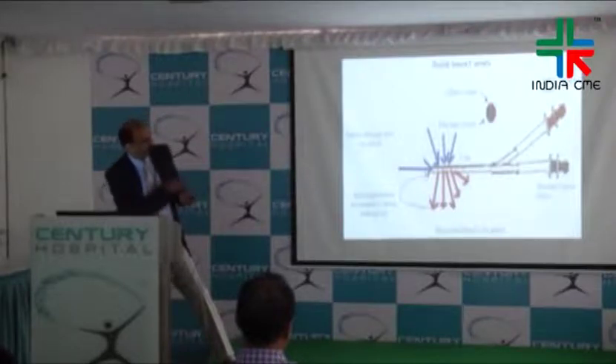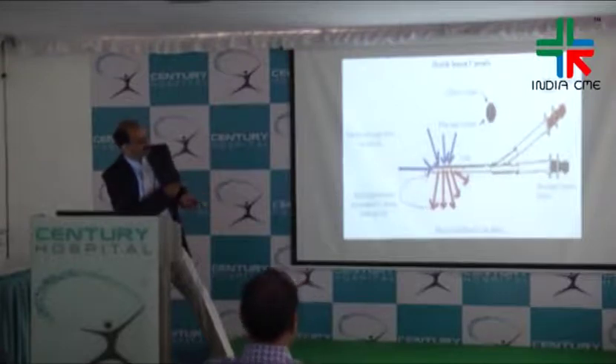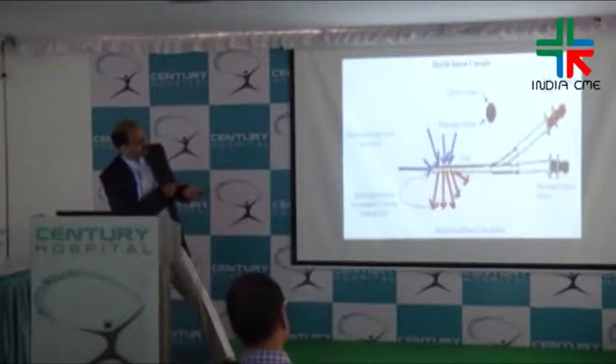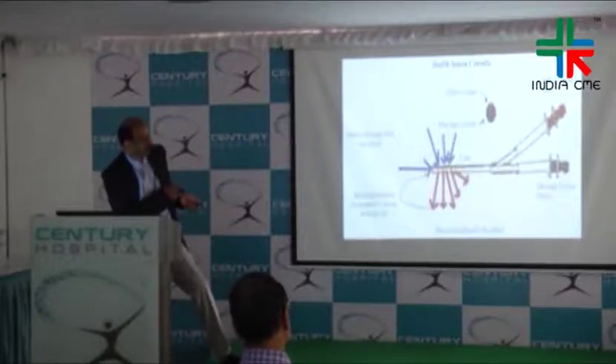The oxygenator circuit is the same again. Once blood is drawn, it goes into the centrifugal pump, through the oxygenator, and comes back to the patient through the return port, where oxygenated blood from the side ports goes into the right atrium.